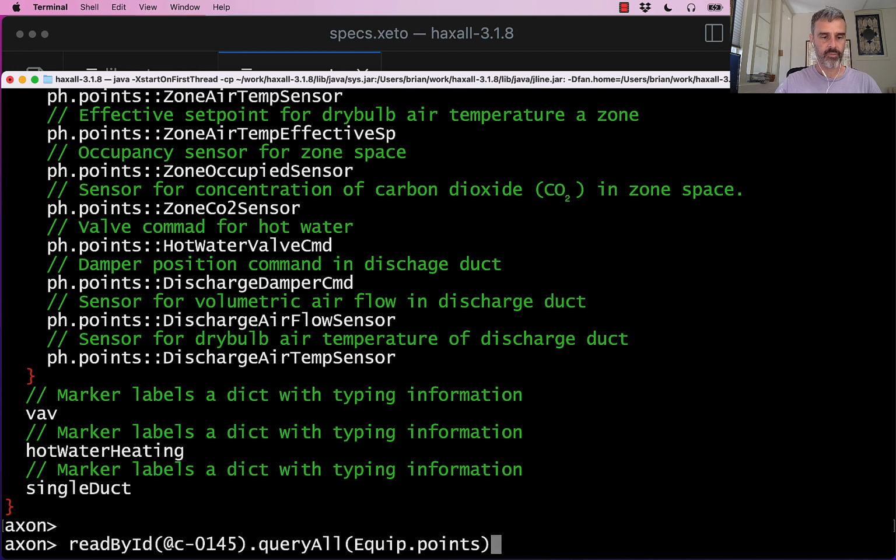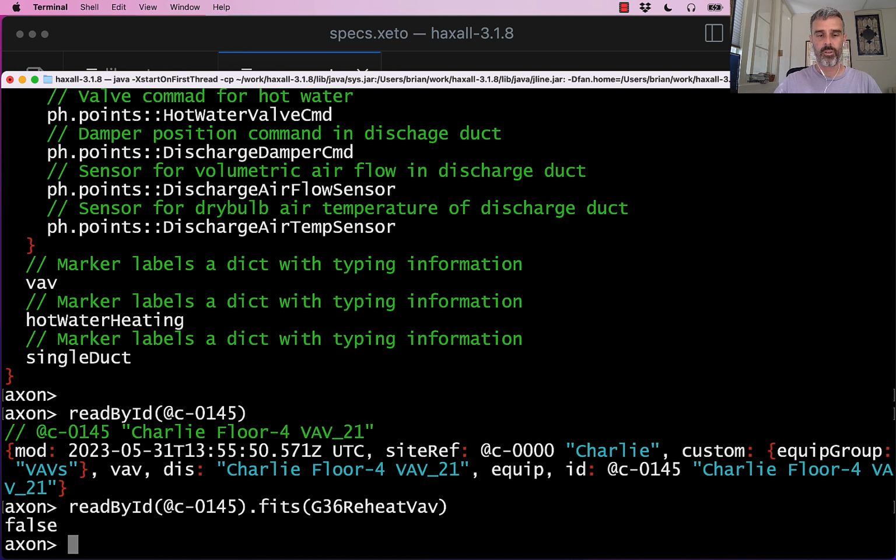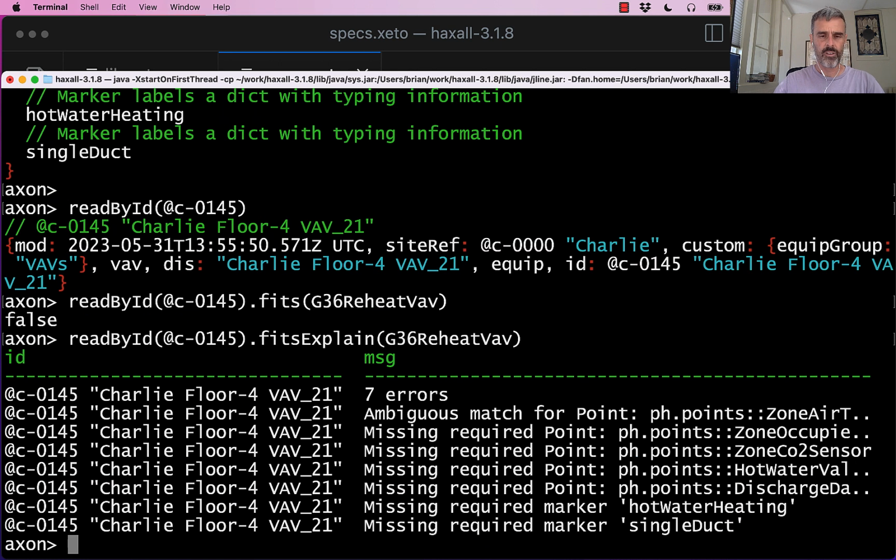Let's make sure this is our VAV. Okay, so this is Charlie VAV 21. Let's see, do you fit guideline 36 reheat VAV? Okay, no. Well, let's ask why. Okay, so we got actually a whole bunch of errors. We got 7 errors. So first of all, we're missing some tags. Okay, I don't even know if these VAVs in this model are supposed to be reheat VAVs, but they're missing the hot water heating tag, and they're missing the single duct tag.